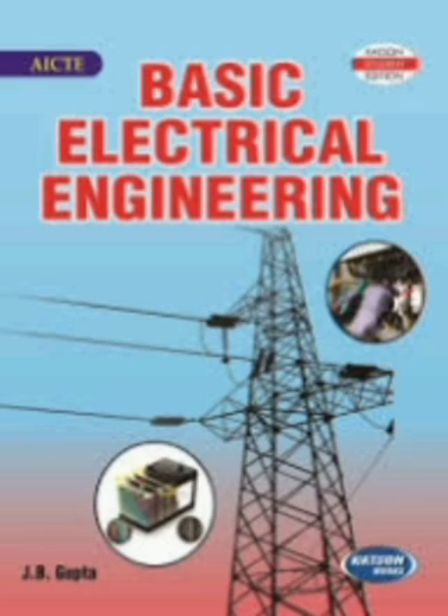The main object of this test is to find out total resistance and reactance of transformer when referred to the winding in which the measuring instruments are placed to conduct this test, to find out variable losses in the transformer, that is copper loss. This test should be conducted at rated current condition. This test is conducted on the HV side while the LV side is short circuited with a thick conductor.